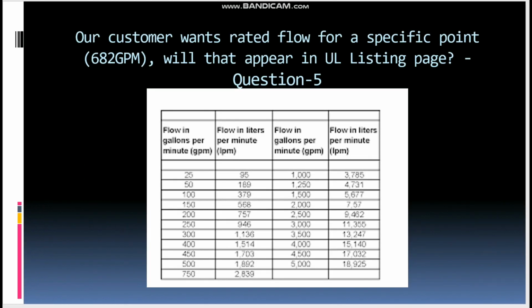Our customer wants a rated flow for a specific point. For example, we have a building with sprinklers and a fire hose reel. Based on the hydraulic calculation, which we will discuss very clearly in a future video, for the time being consider we have sprinklers and a fire hose reel cabinet. The sprinkler flow based on the hydraulic calculation is 582 GPM, and I consider two residual fire hose cabinets, so I added 100 GPM, so the total is 682 GPM. So will that appear in the UL listing?